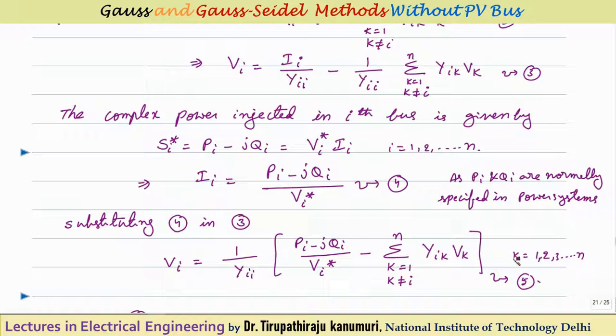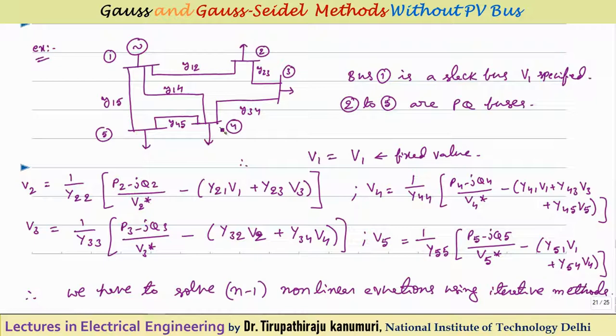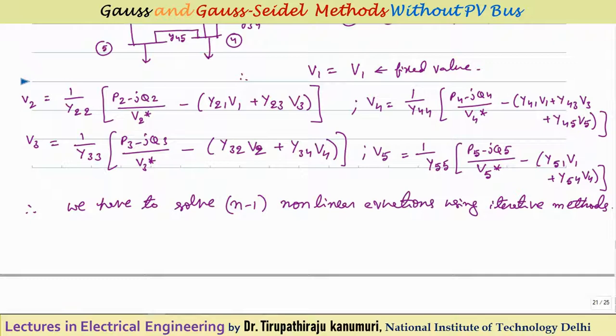Since Vi appears on both sides, we go for an iterative method to calculate all bus voltages. Taking the example of a 5-bus system, all buses are assumed to be load buses except one slack bus — we always need at least one slack bus since we do not know the losses beforehand. The slack bus has a specified voltage magnitude and angle of zero degrees. There is no PV bus in this case to keep the analysis simple.